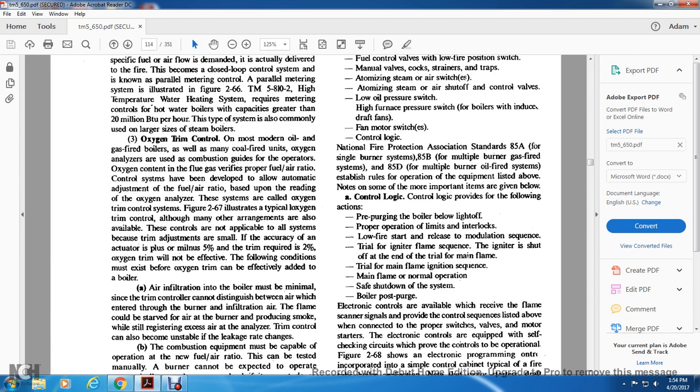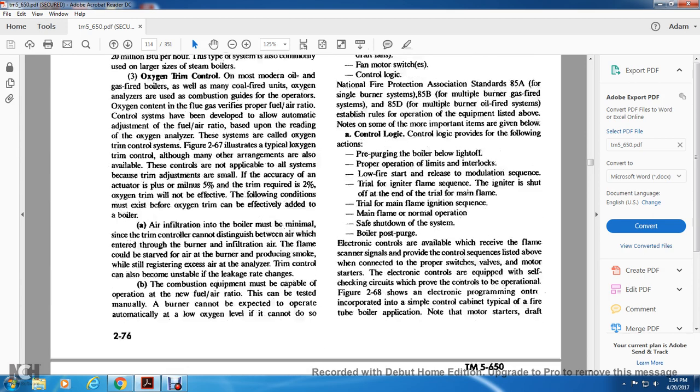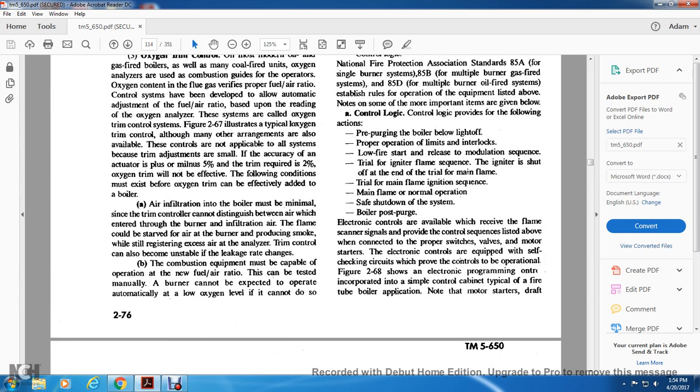Pre-purging the boiler before light off. Proper operating limits and interlocks. Low fire start with release to the modulation sequence. Trial of the igniter flame sequence. The igniter is shut off at the end of the trial for main flame. Trial with the main flame ignition system. Main flame and normal operation. Safe shutdown system. Boiler shutdown. Post-purge.